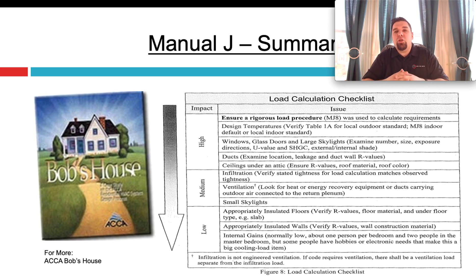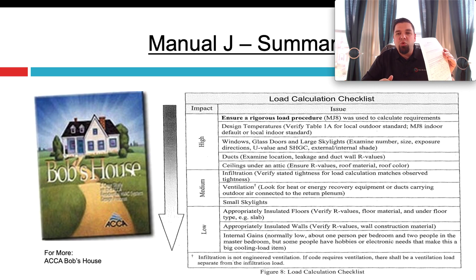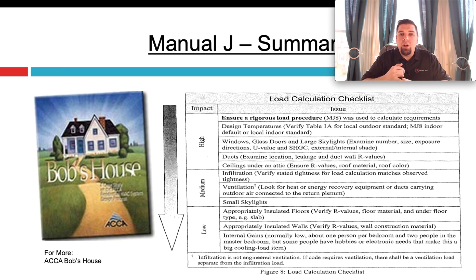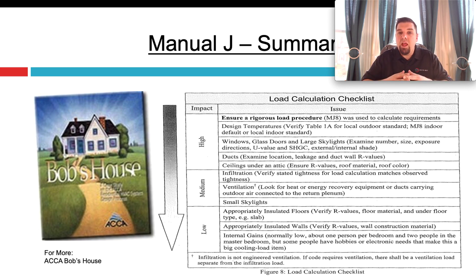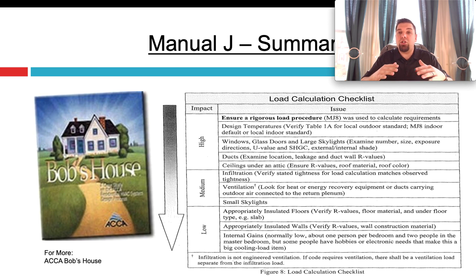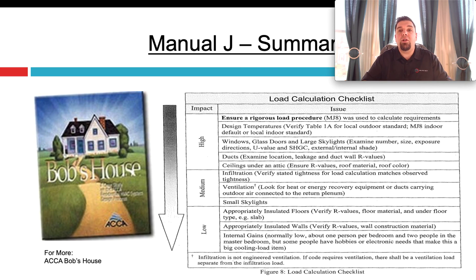A few things when you talk about site survey: the things you want to spend the most time on and make sure they're correct are your design temperatures, the fenestration we talked about, your ductwork — make sure you examine the location, how well it's sealed, and what the R-values are — and then any ceilings that are under attics. These are very important, large surface areas, and these are the things that impact the load the most. This is where you spend the most time in your site survey.